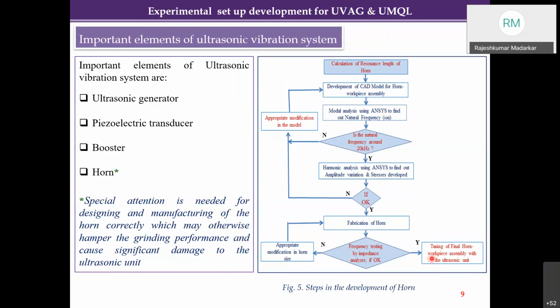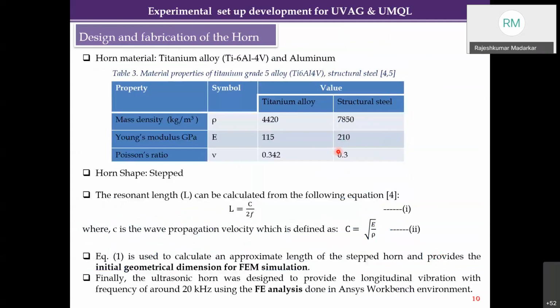And then before actually connecting your horn to your ultrasonic unit, you just want to check the frequency with the help of an impedance analyzer or other methods. And once you are sure that your horn is correct, only then do you attach it to your ultrasonic unit, because if it is not correct, it can hamper your ultrasonic system. So I had developed this horn, and these are some of the details about that.